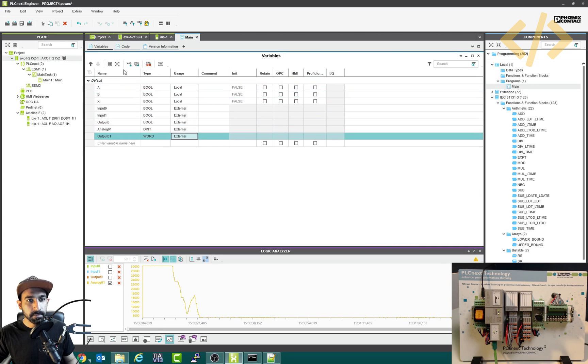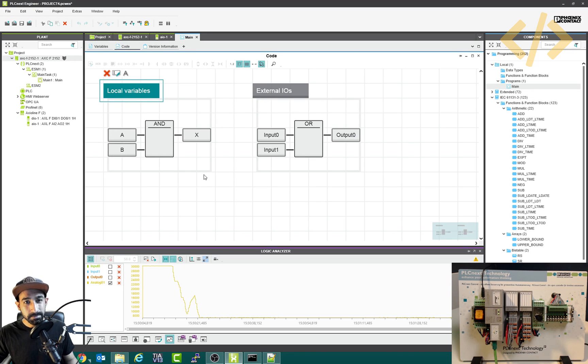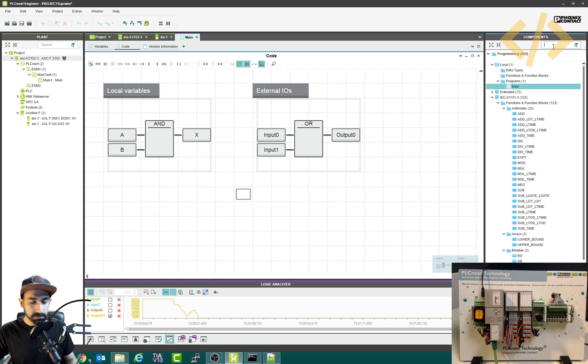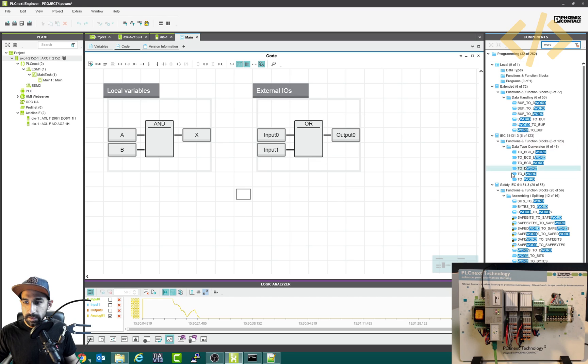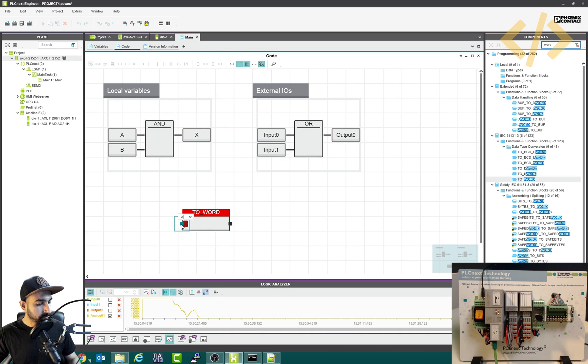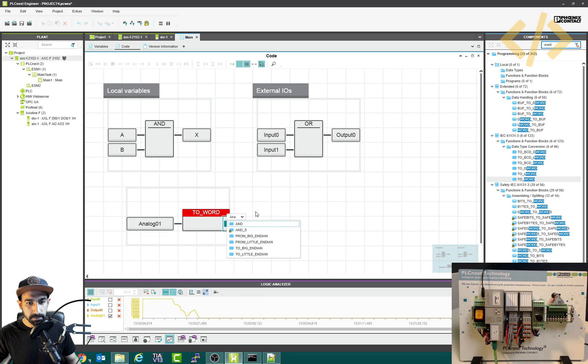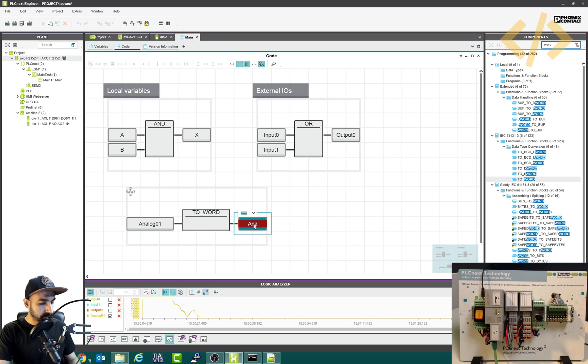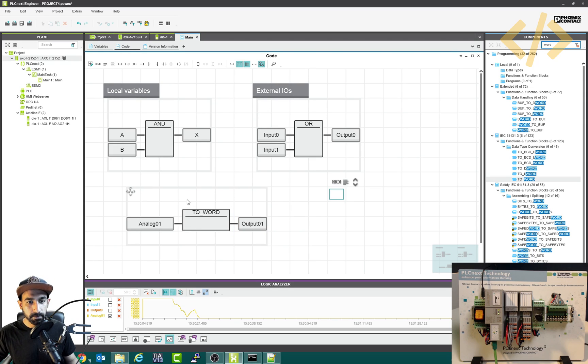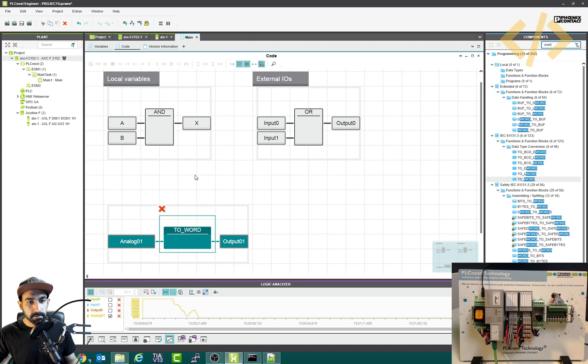Go back to main and to the code. I want to move analog input to analog output. My analog input is double integer but I need the output as word, so I'll search for instructions — type 'word' and you'll see 'to word', which is a data type conversion to word. I'll take this instruction. In the input I'll put 'analog input zero one', and in the output I'll use 'output zero one'. I'll add a small comment: 'download IOs'.